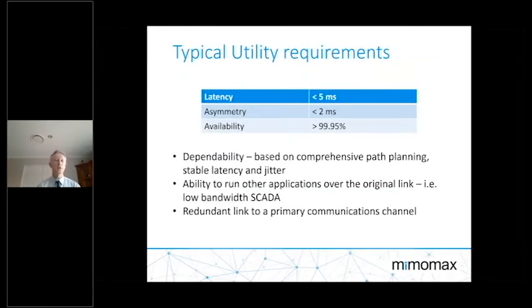So typical utility requirements: what we're seeing is latency that's less than 5 milliseconds for the communications link, asymmetry that's less than 2 milliseconds, and availability that's up in the order of 3.5 nines, but typically 4 nines in terms of availability for teleprotection networks is typical.